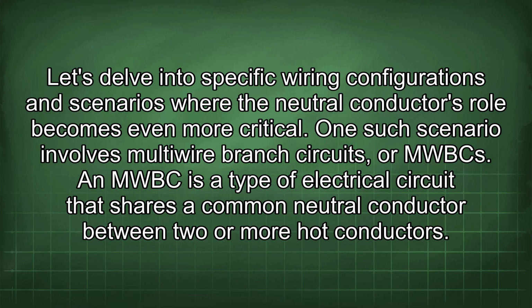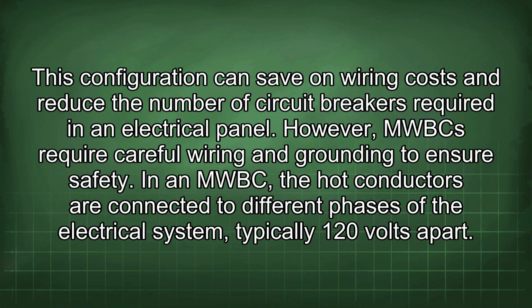One such scenario involves multi-wire branch circuits, or MWBCs. An MWBC is a type of electrical circuit that shares a common neutral conductor between two or more hot conductors. This configuration can save on wiring costs and reduce the number of circuit breakers required in an electrical panel. However, MWBCs require careful wiring and grounding to ensure safety.